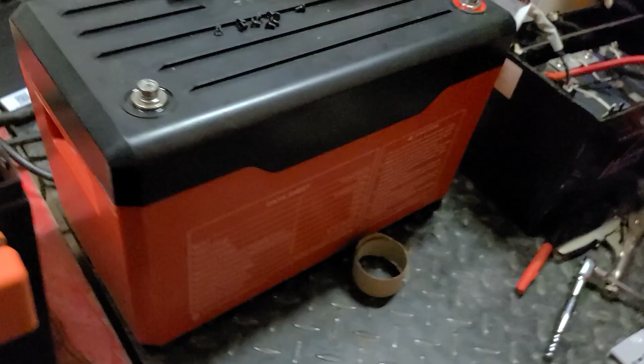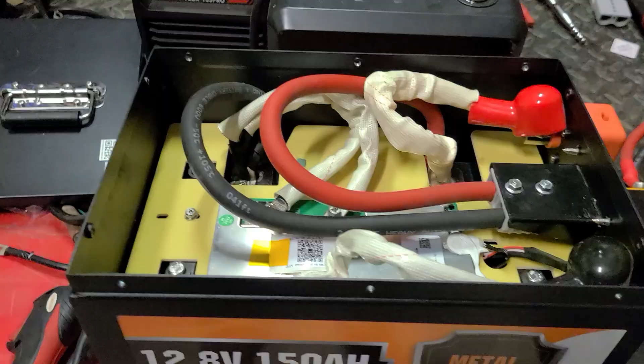Now this inverter's specs called for 2-aught cable, and I didn't really want to try to maneuver them big cables in here. So I got 2-gauge cable, but with the short run they have to make, and this isn't going to be putting out 3,000 watts for a steady hour.